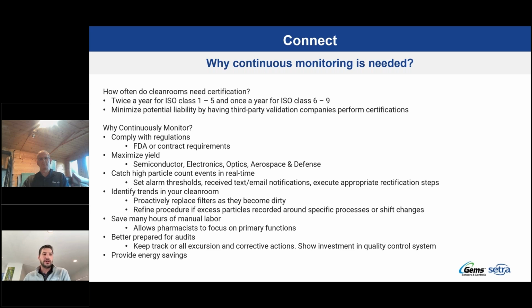We already talked about the saving of manual hours, and being better prepared for audits. So whether it be your customer that's auditing you, or an accreditation board that's coming to audit you, having a continuous monitoring system always helps you be best prepared for that. And lastly, it can provide energy savings as well. So if you did have a continuous particle count monitor in your clean room, and you had to maintain an ISO 6 environment, for instance, you could essentially turn down your FFU levels and still maintain that ISO 6 environment by continually sampling that particle count and verifying, hey, we could run our fan filter units at 50% and still maintain the cleanliness that we're looking for, and that will provide some energy savings.